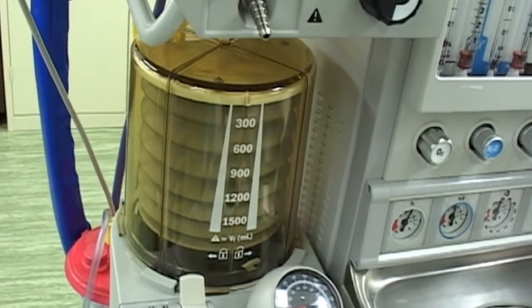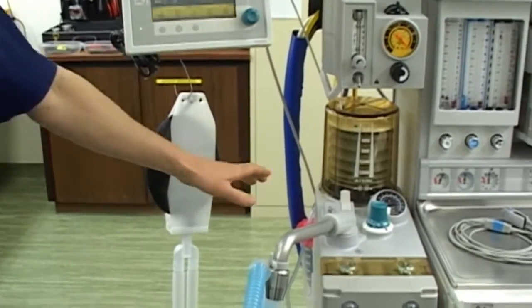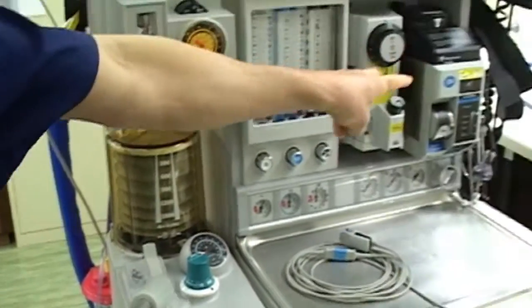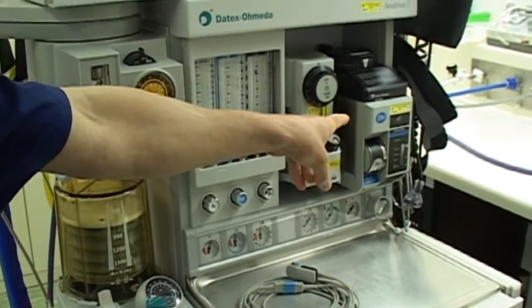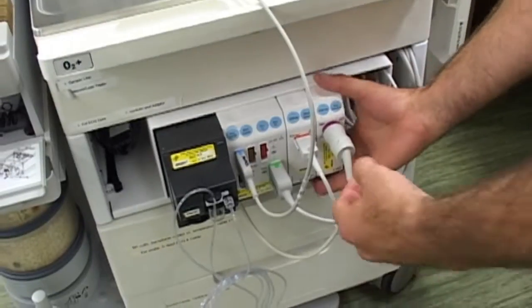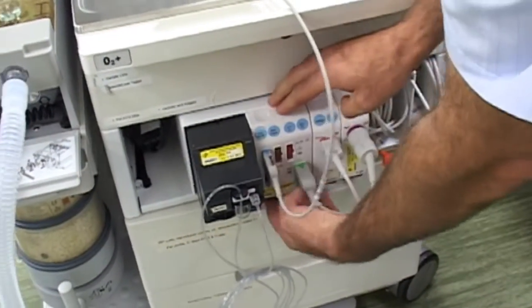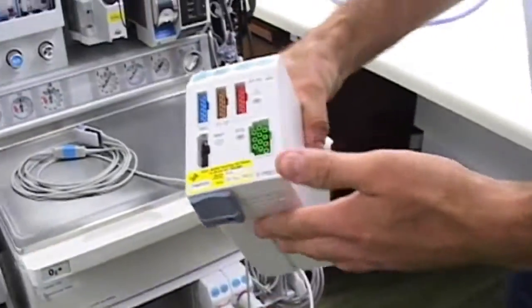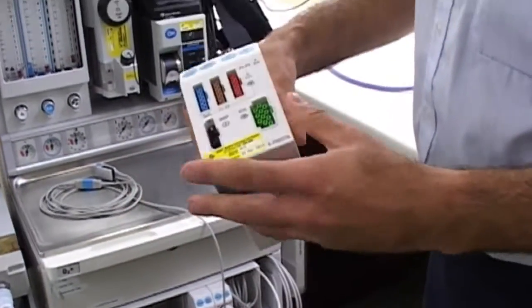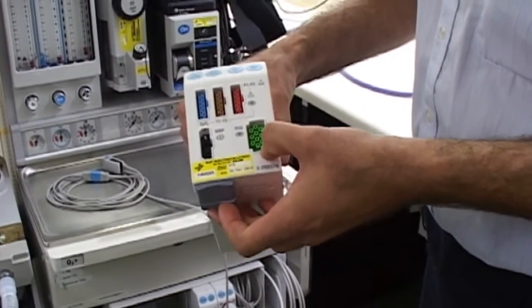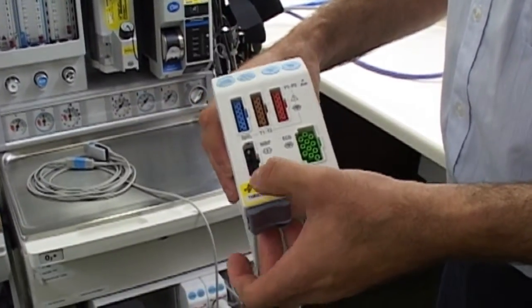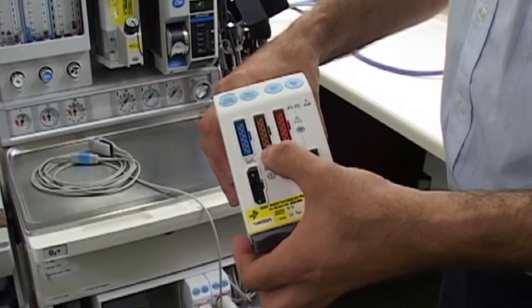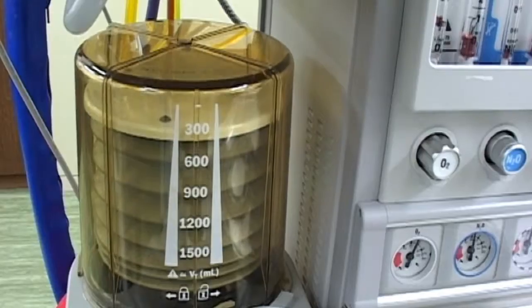I have an opportunity now to look at the gas side of this, which is the ventilator here. And we've also got two anaesthetic agent delivery units there. These are all modular devices. What we'll do is we'll just take a module out. This module, when it's hooked into this rack, will actually measure all your vital signs. So it'll measure your ECG, non-invasive blood pressure, your oxygen saturation, temperature, and invasive blood pressures. And we can check all those with our simulators, making sure the correct measurements are coming up, making sure they're accurate.